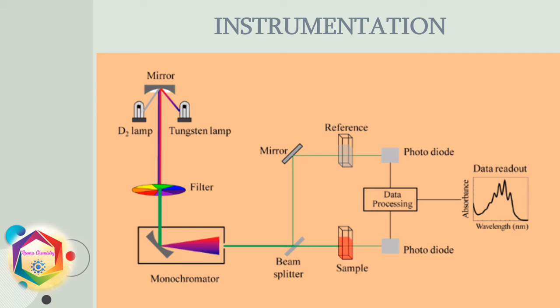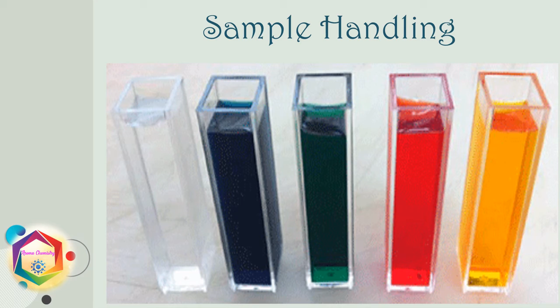Sample handling. UV visible spectra are usually recorded either in very dilute solutions or in the vapor phase. Quartz cells of 1 cm square are commonly used for recording the spectra. The sample is dissolved in some suitable solvent which does not itself absorb radiation in the region under investigation. Commonly used solvents are cyclohexane, 1,4-dioxane, water and ethanol. The chosen solvent should be inert to the sample.